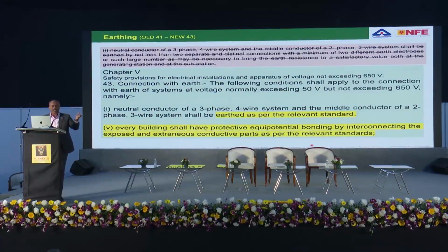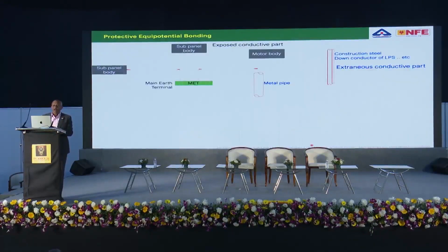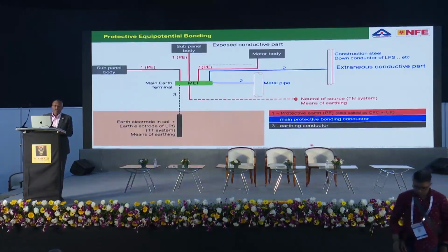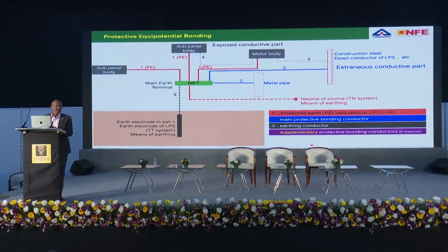Earlier, it was in a different style. Now, it is made very simple. What does it mean? Your building has got a lot of metal parts, dead metal parts, I would say. Dead metal parts in the sense, metallic parts, maybe the casing of a class 1 electrical apparatus, or maybe the metal structure, something like this. We have the air conditioner duct, we have the metal columns. Every building shall have an equipotential bonding, meaning all the dead metal parts must be interconnected in such a way that simultaneously accessible metallic parts don't have a shock voltage.